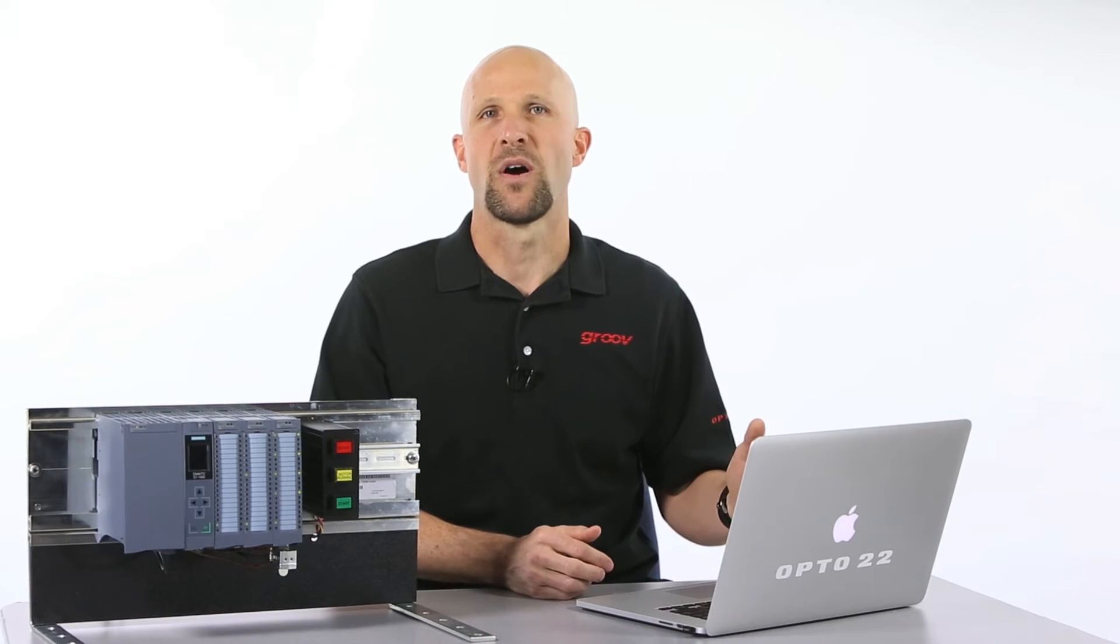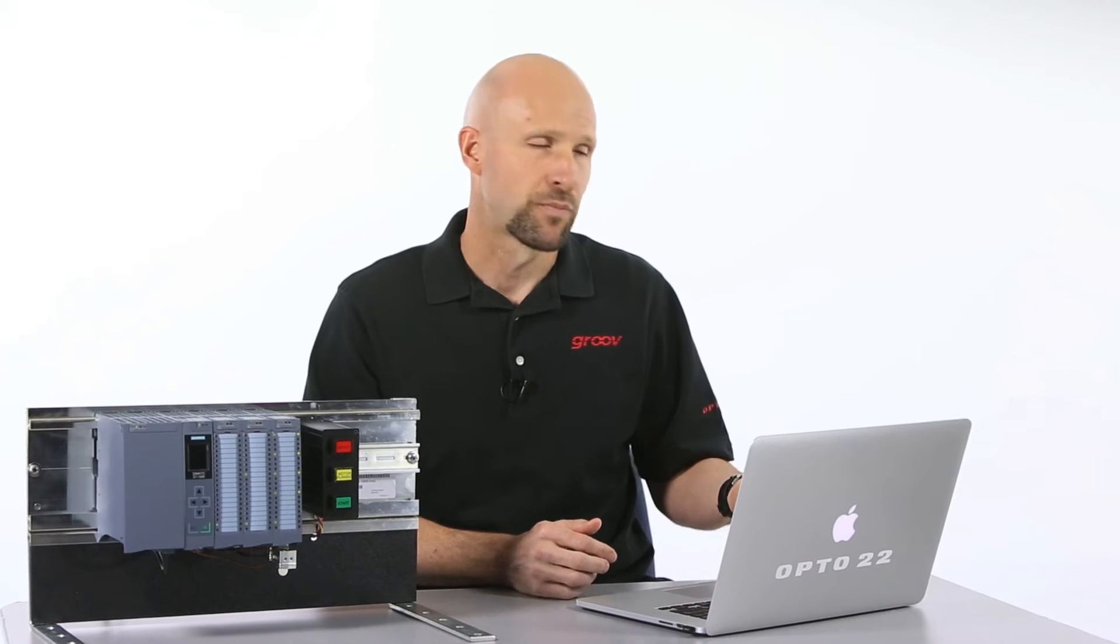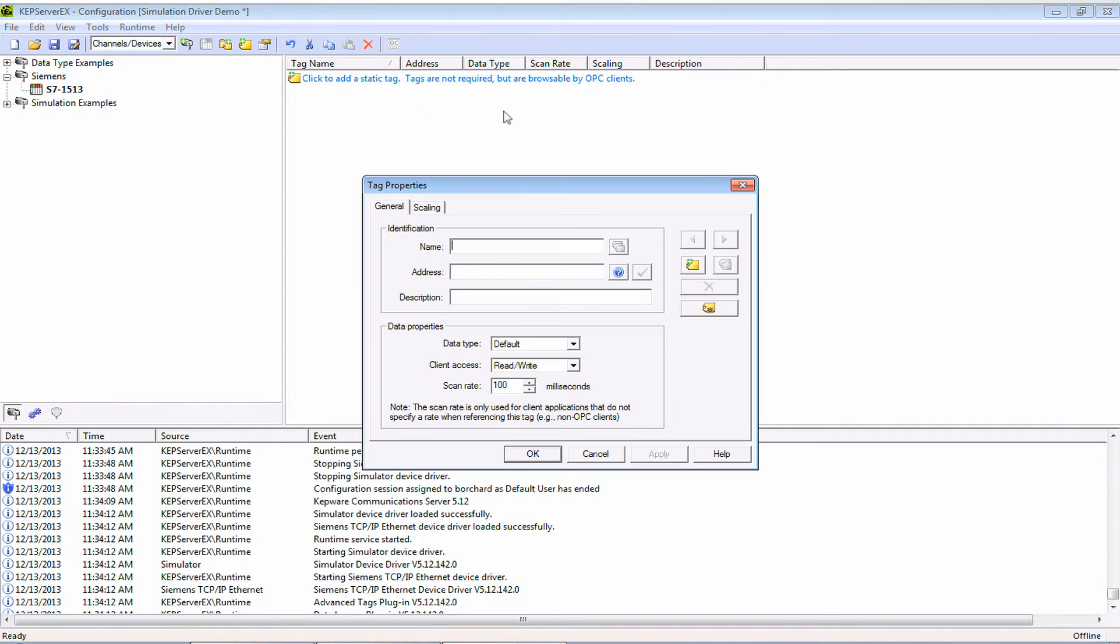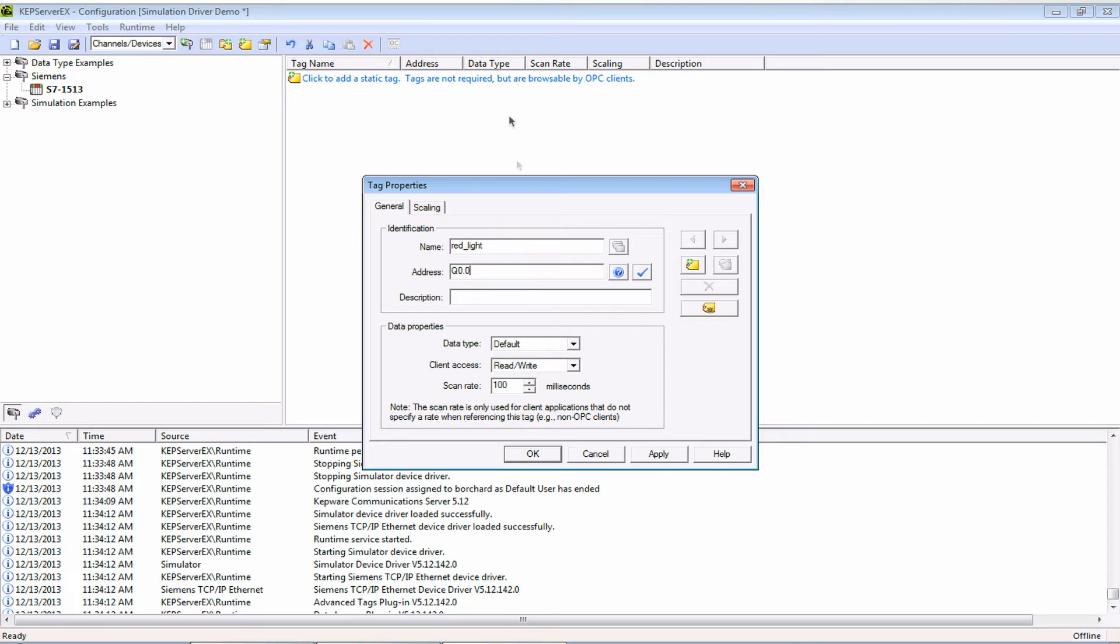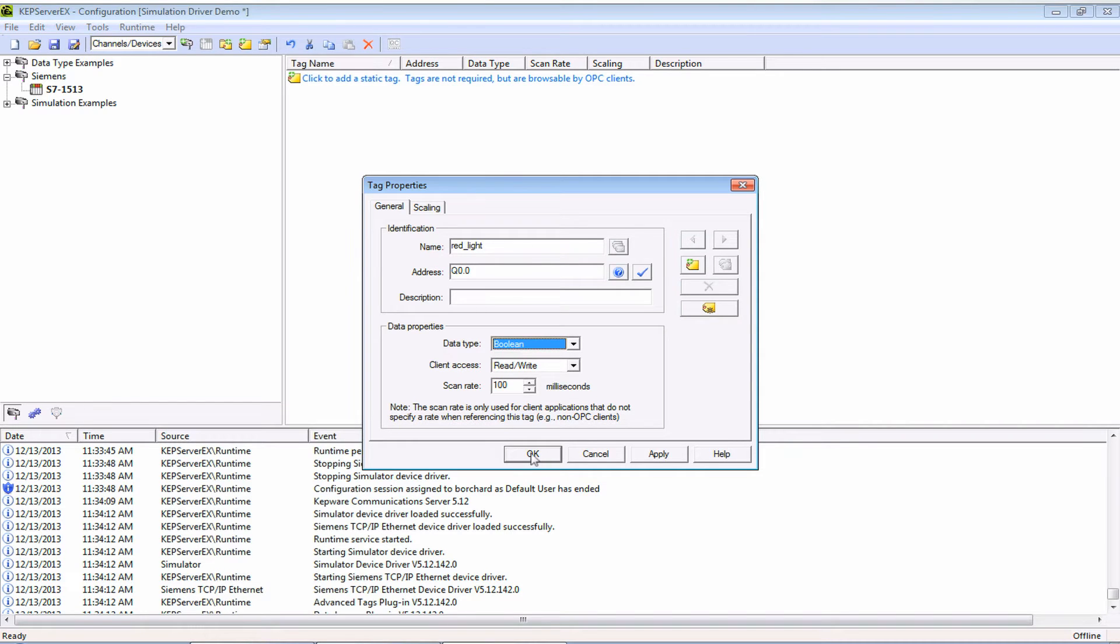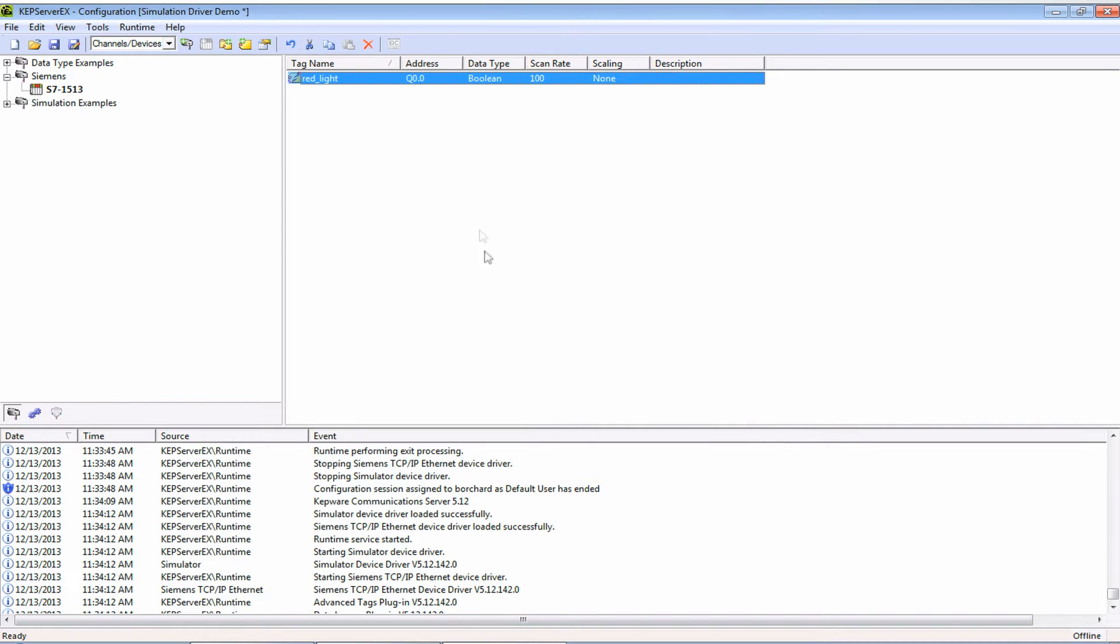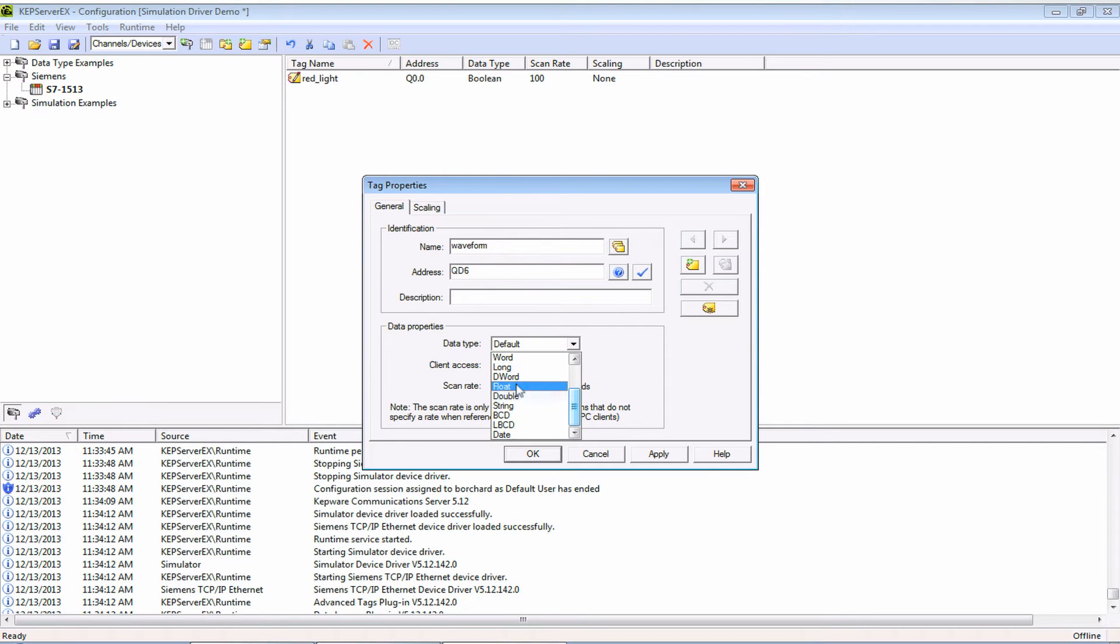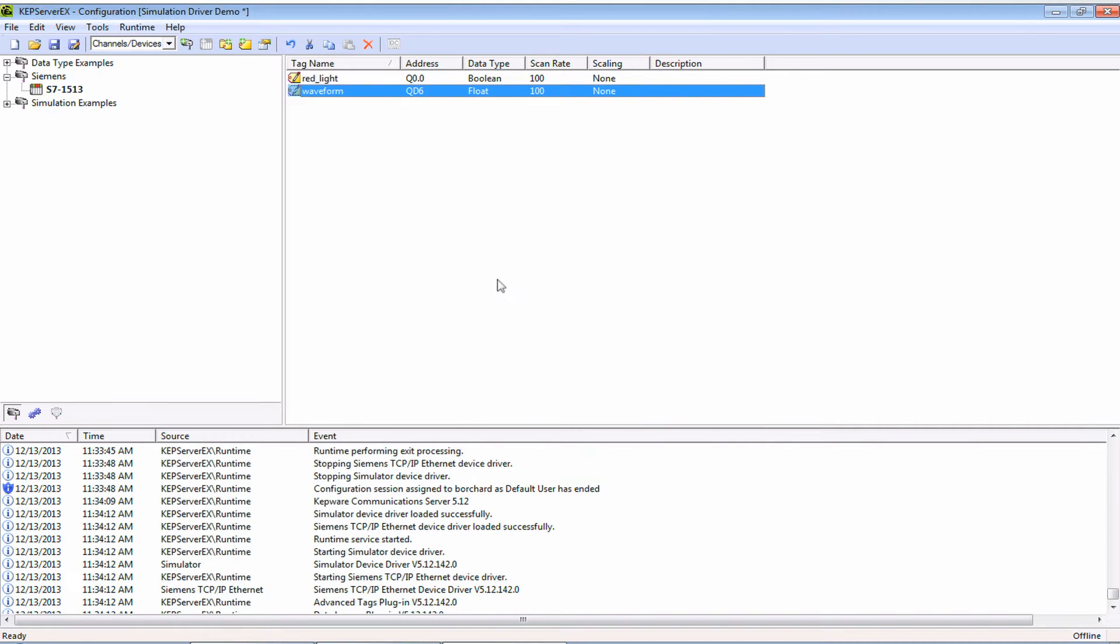So now that we have a channel and a device let's add a few tags. Right click and select new tag and I'm going to add a digital output. Give it a name and put the address in. In my case it's the first output of the card so it's called Q0.0 and the type is a boolean. Now let's also add a variable. Right click and select new tag, give it a name and the memory address is QD6 and the type is a float. Okay that's it, I'm done with step one.